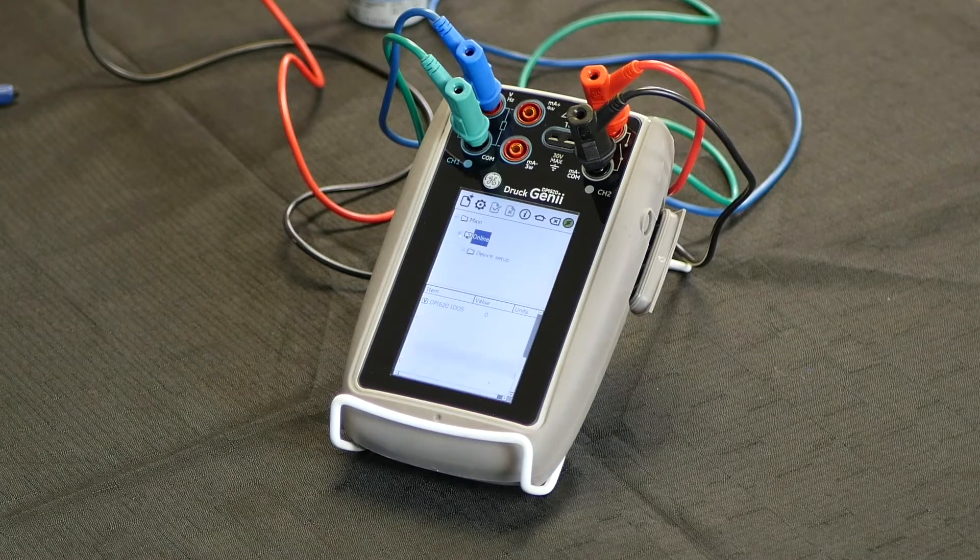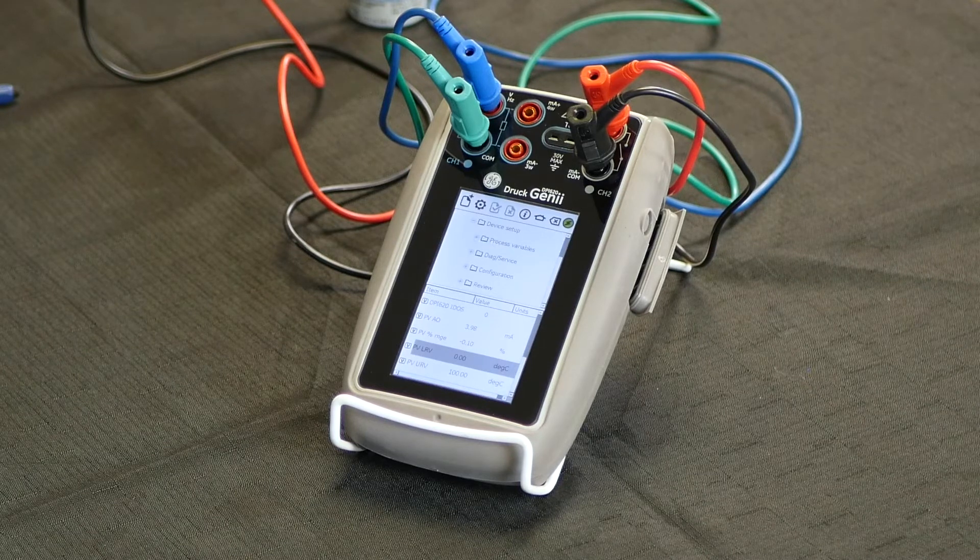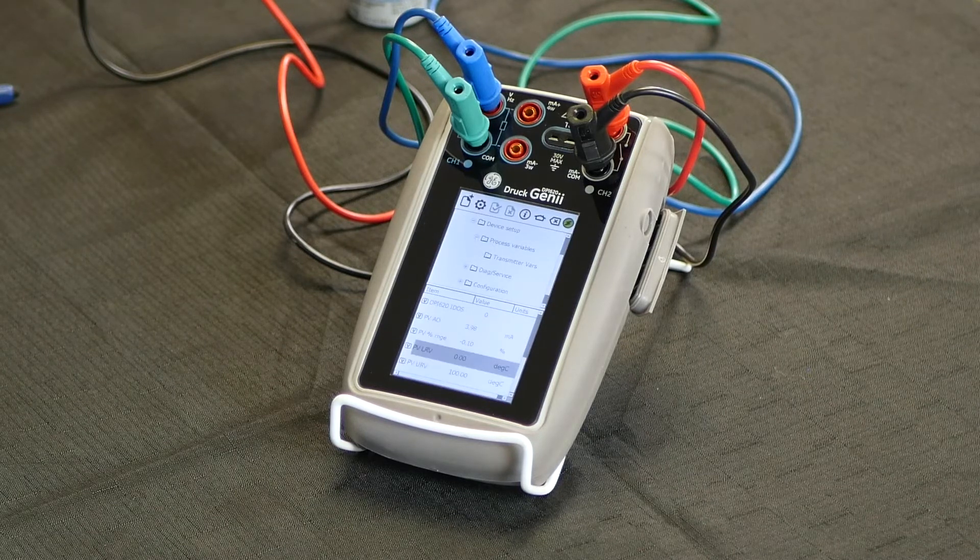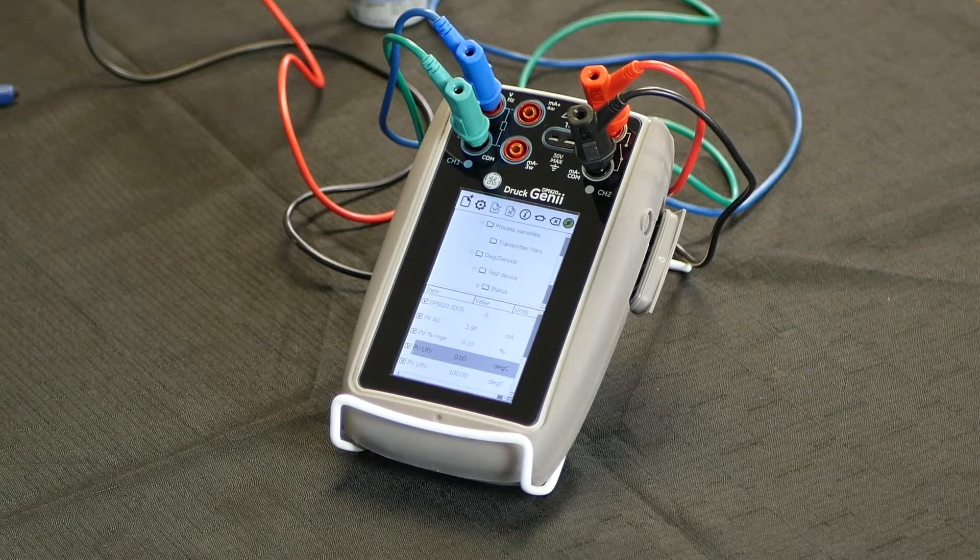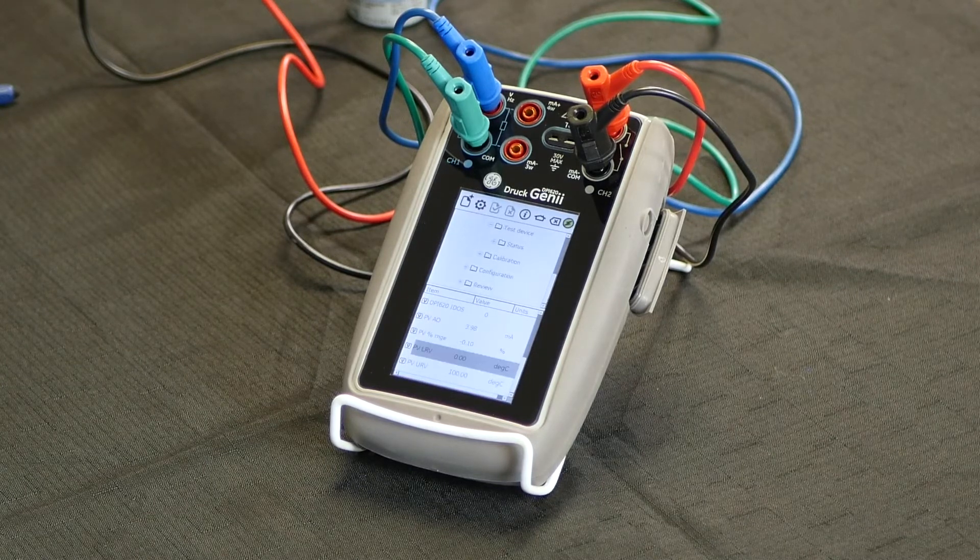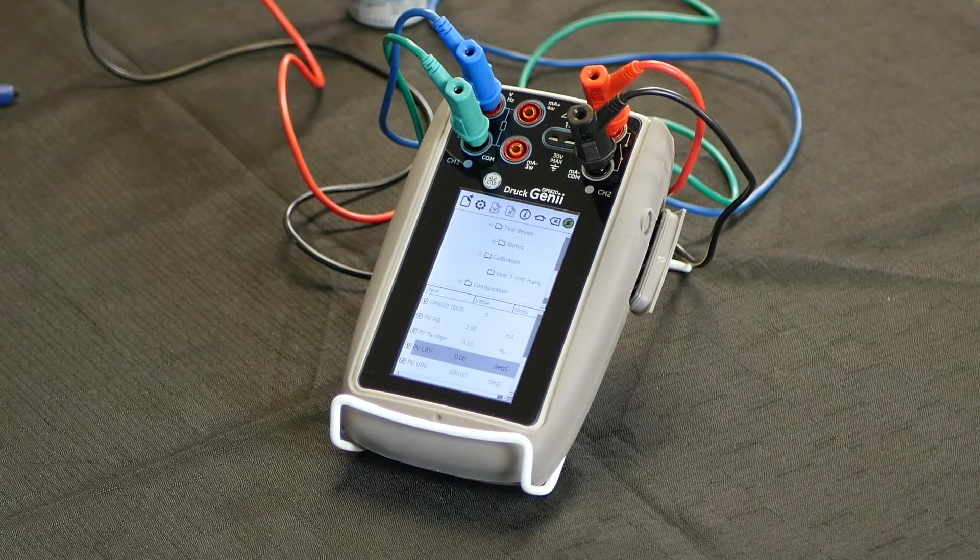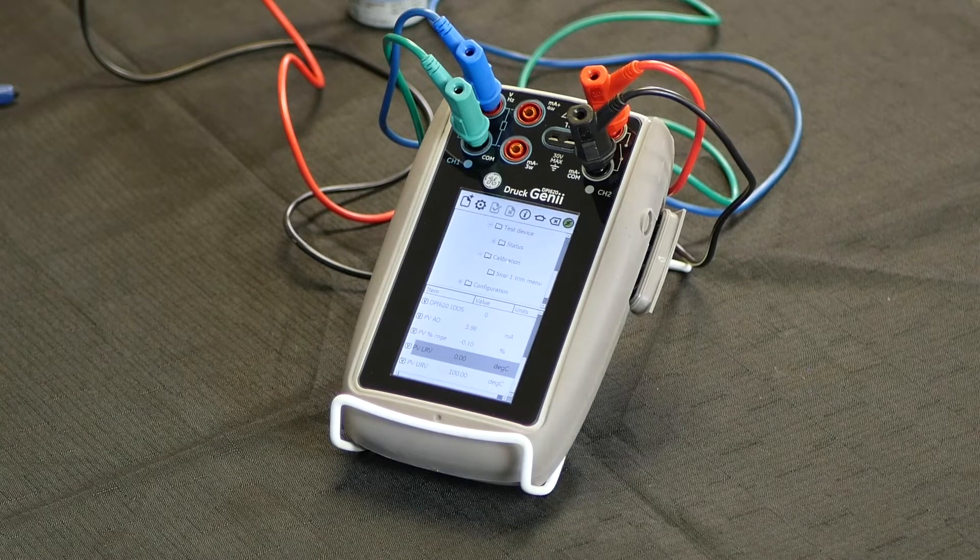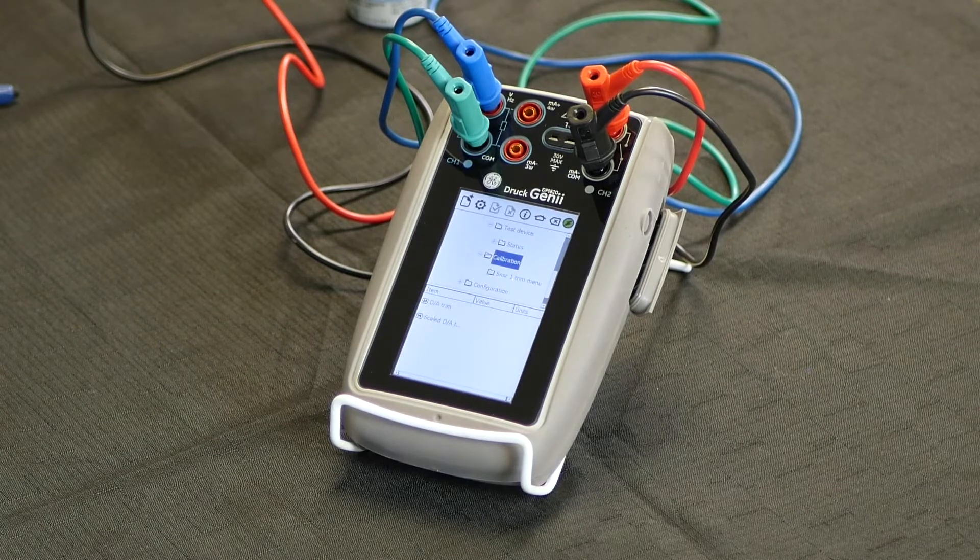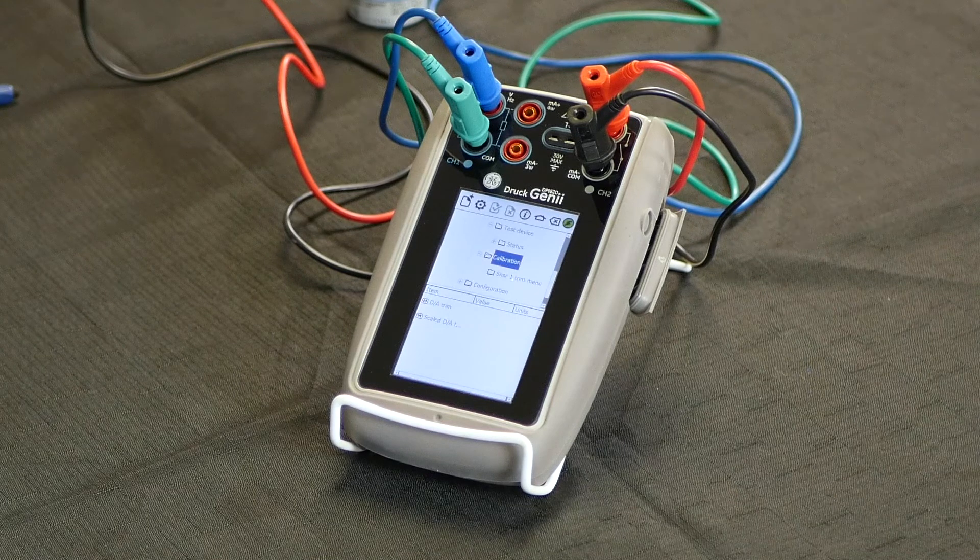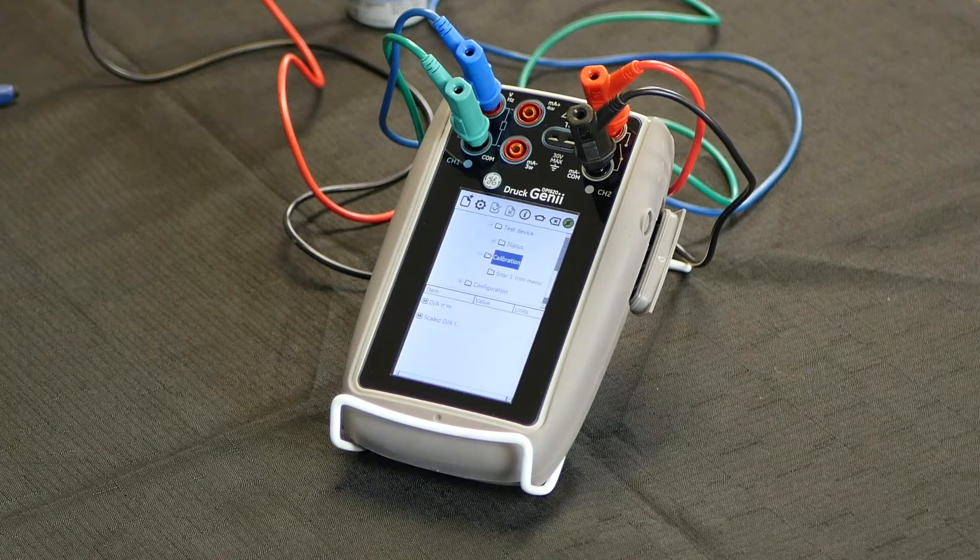To expand the menu tree to show you that it truly is a fully functioning HART communicator, you can see the multiple levels of the menu tree available. To show you one of the more commonly used features and functionality of a HART communicator, we'll go into the calibration mode and you'll see that you have the ability there to perform a sensor trim method and or a digital to analog trim method.